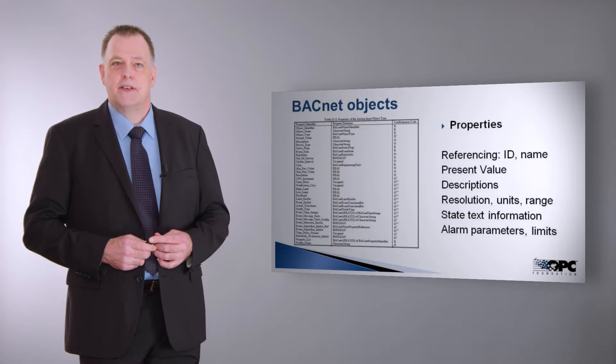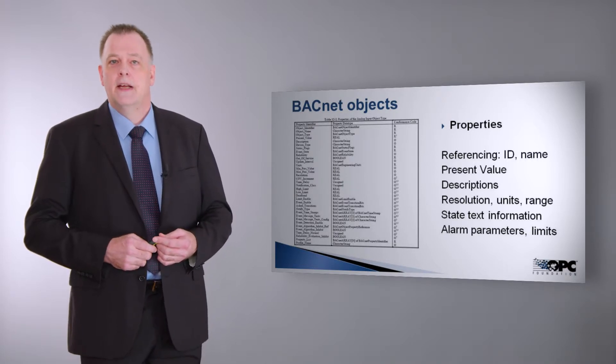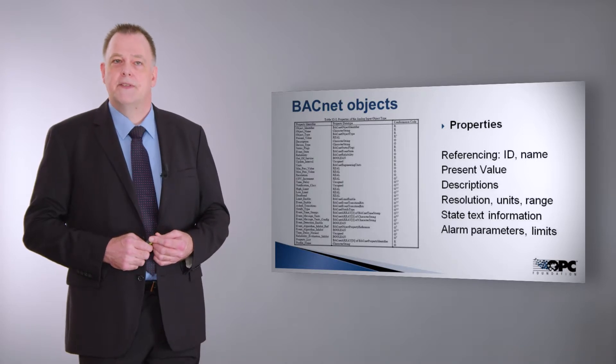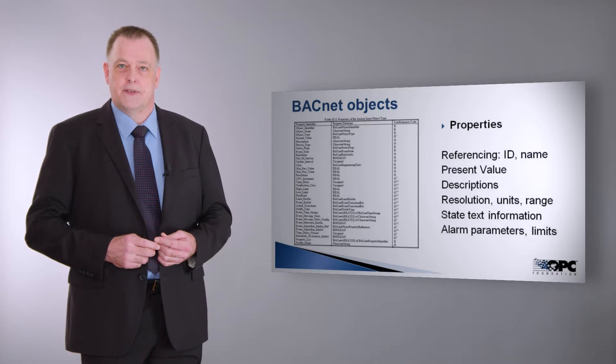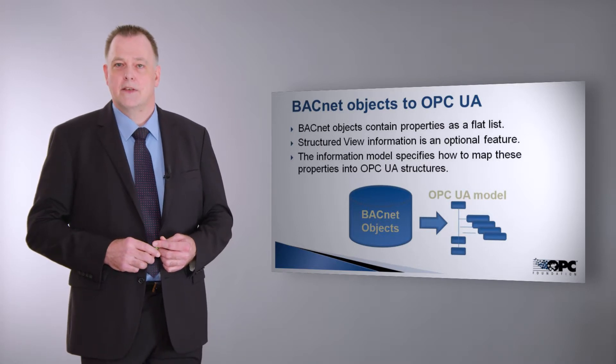In this picture we see a BACnet object — in this case an analog input object with its properties. On the right-hand side you find a short overview of which properties are presented from building automation. This includes the reference of the object, so the name and the ID, the present value which is most likely the most important information, but of course also information like the description text, the limits, the units, the range, and of course the alarm status of this object. In BACnet, devices objects are flat with no hierarchy information, even though there's an option called structured view which may be applied to BACnet devices to present the user hierarchy — the facility manager's view to the data points. In OPC UA we already have structured data types, so we can use this mapping to map structured data into the OPC UA structures.